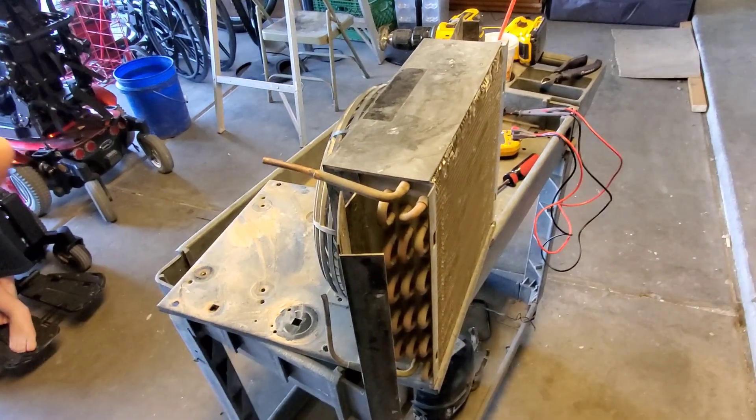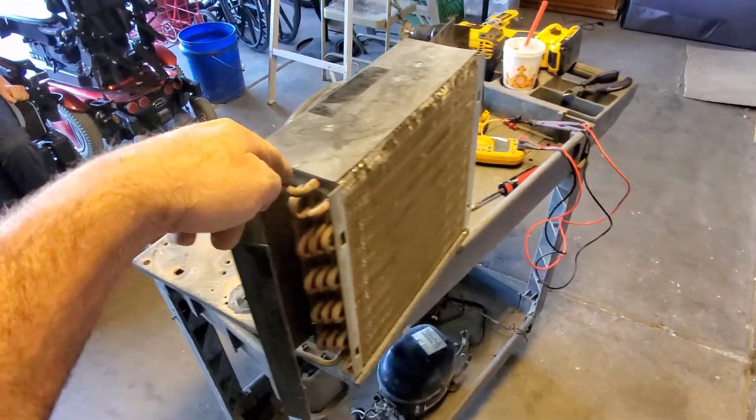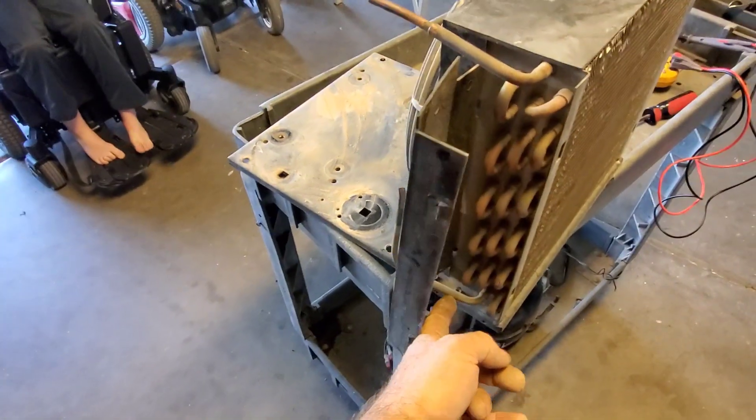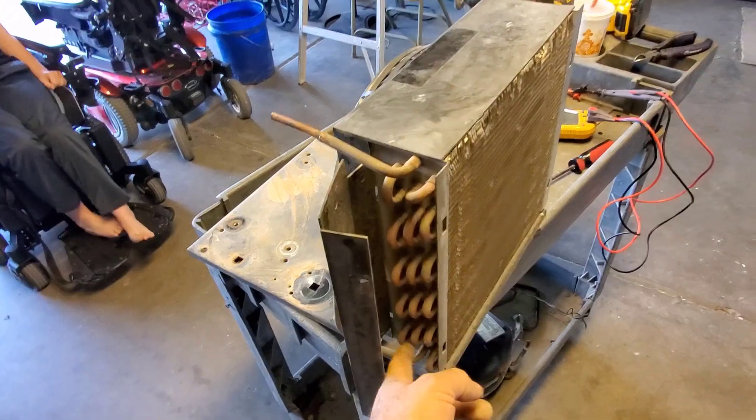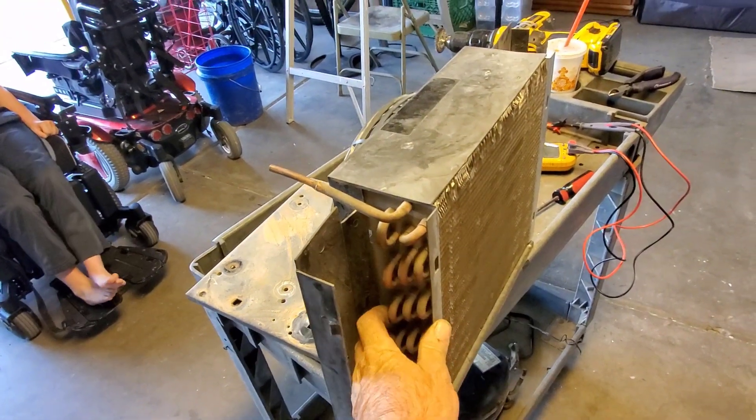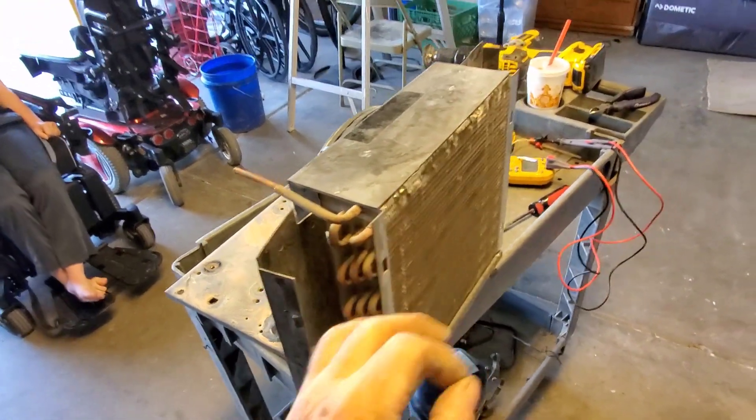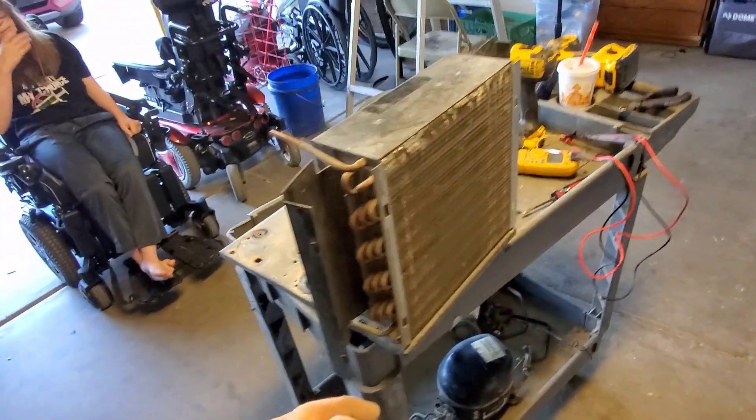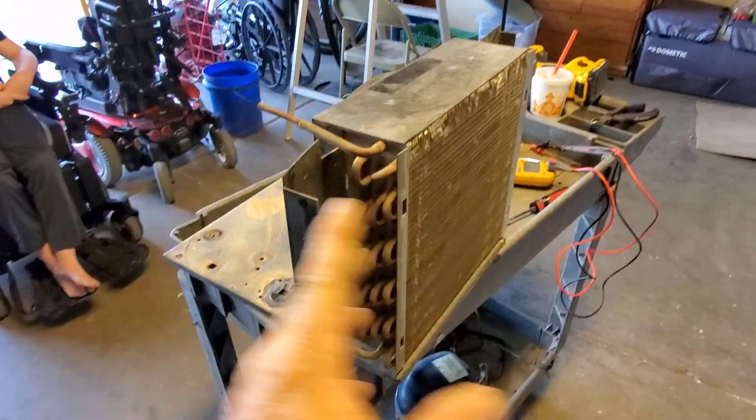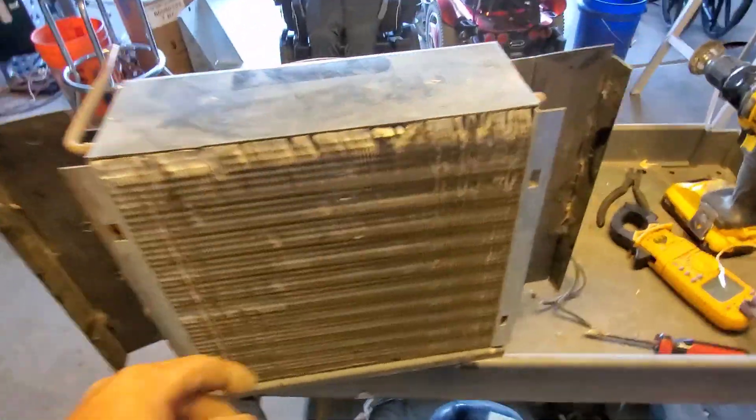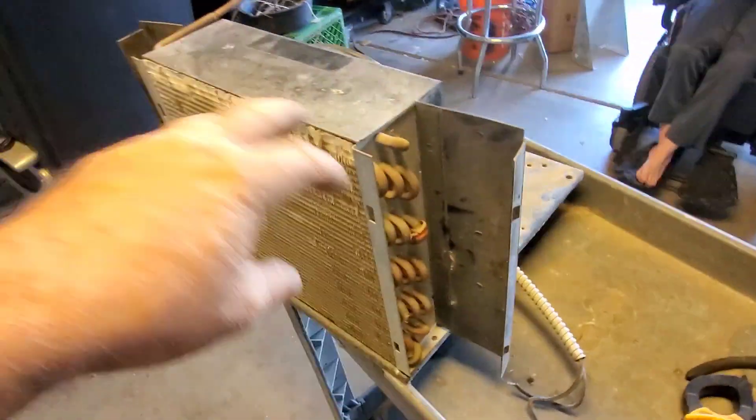Oh, I didn't even think about it till now. This is piped as a simple condenser—hot gas going in here, goes back and forth, and then it's condensed liquid coming out the bottom. So it would not make a very efficient evaporator. I'm gonna stare at it for a few minutes off camera and maybe see if I can make it into split circuits.